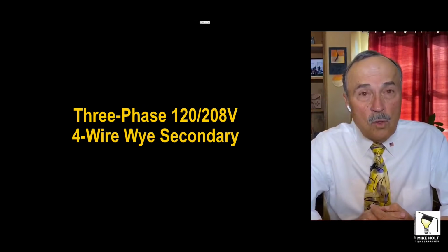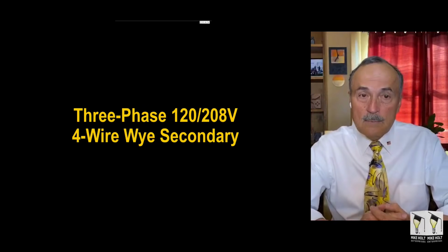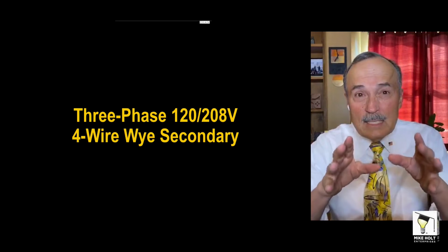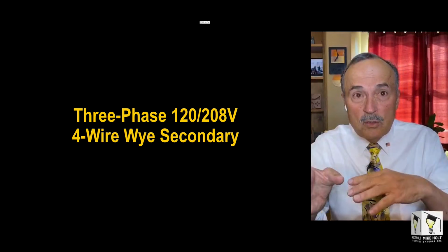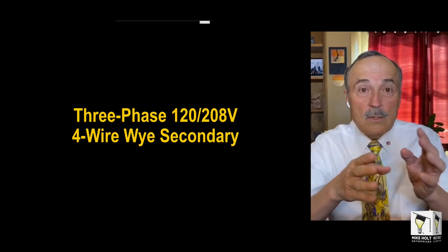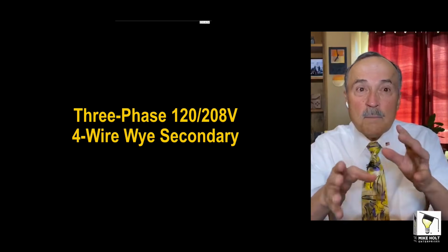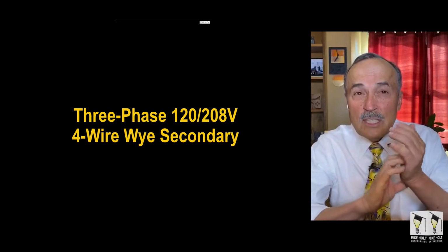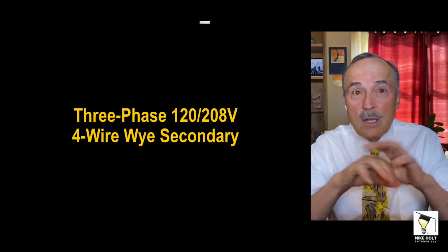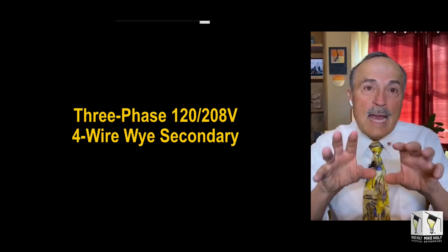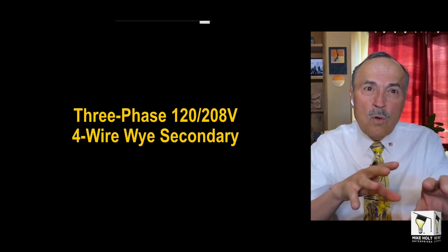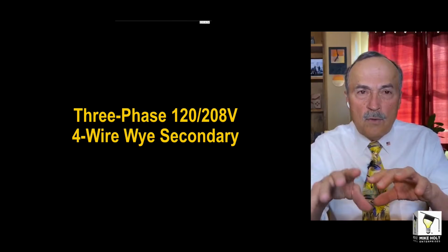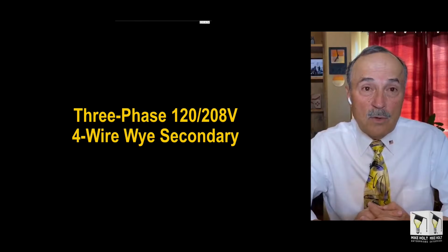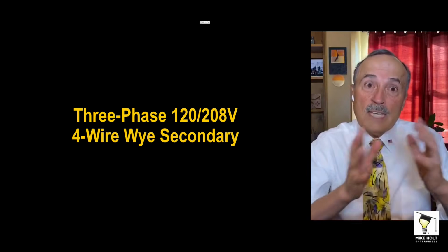3-phase, 120/208, 4-wire wye system. Now look, somebody has decided which system they're going to be using. Single phase, 3-phase, 120/208. Somebody's making that decision. And a lot of that decision is a function of the electric utility, what they have available at that location. So don't worry about, well, how do I know all these different voltages? Well, if you're not designing them, it doesn't really matter. If you are designing them, then you're going to have to get with the utility.